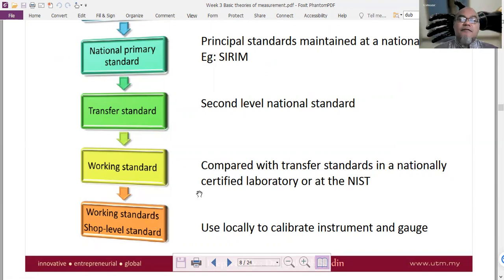That small weights. Usually we have it in one single box, different types of it. Depending on the measurement we want to do, we need to do that calibration. For example, sometimes the balance will behave differently when you measure small weight compared to when you measure larger weight. Okay, calibration is something you need to do. And then that working standard itself has to be calibrated as well. Yeah, how do we know that standard weight, for example, 100 gram is really 100 gram?